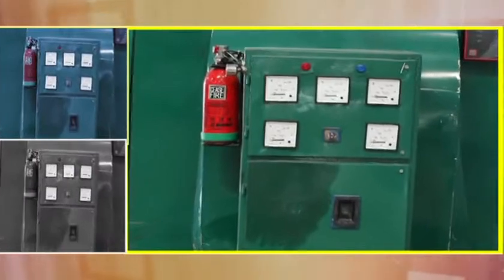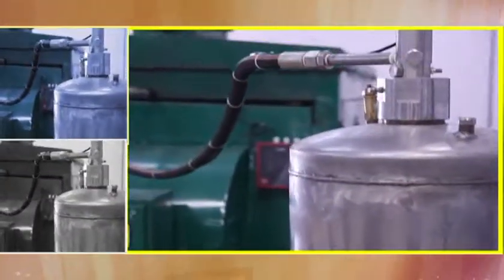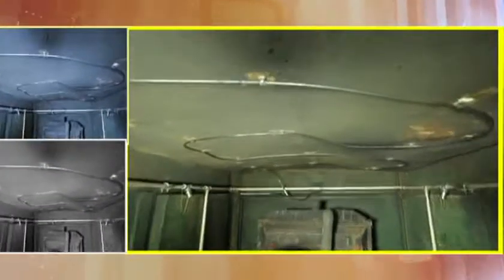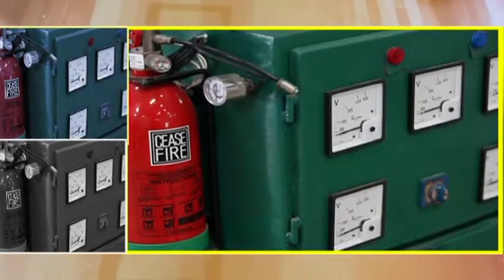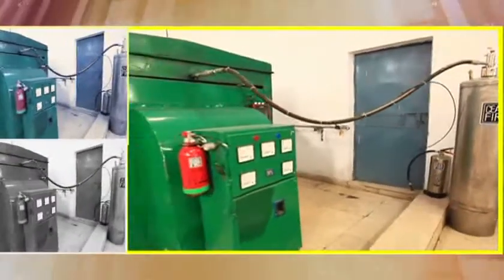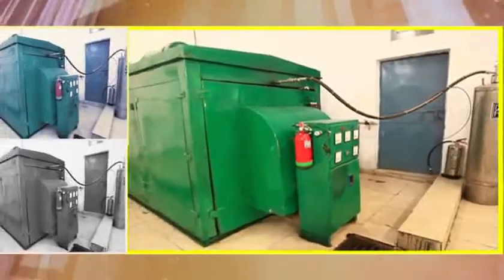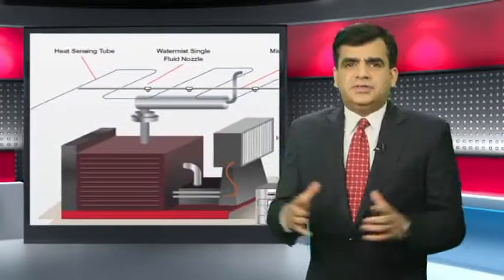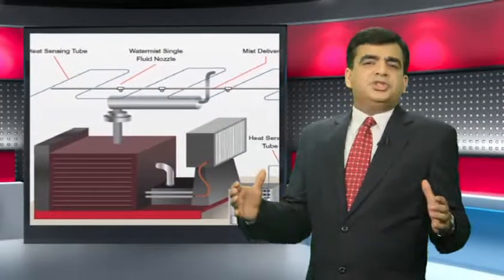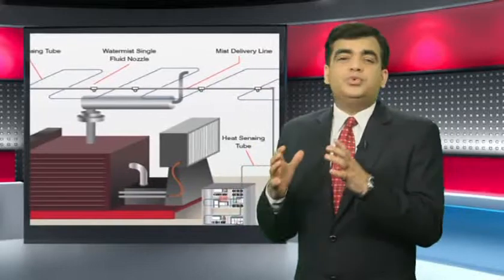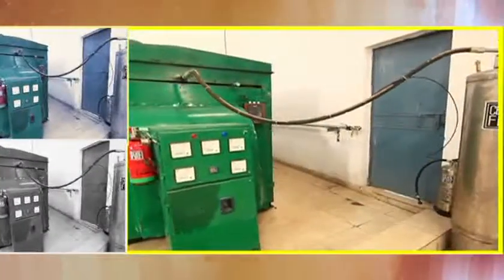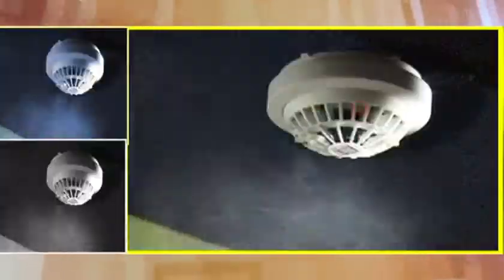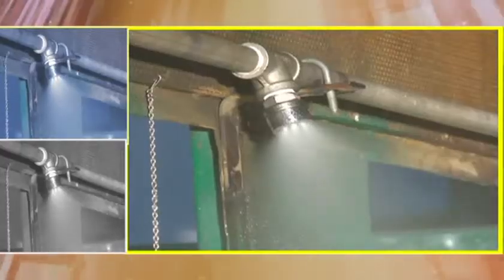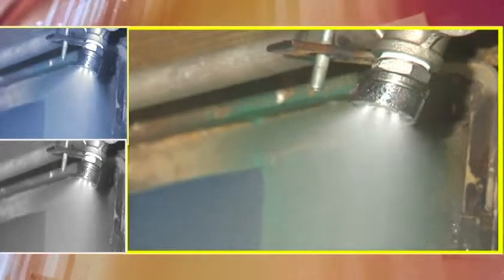And what's great is that these two systems, the one protecting the generator and the one protecting the control panel microenvironment, work simultaneously, ensuring total coverage. Now that we've seen all parts of the system, let's see how it all comes together to fight a real fire. Here's the pulse mist system in action. As soon as it detects the fire, the Ceasefire Generator Auto-Quell System starts up and puts out the fire in just a few minutes.